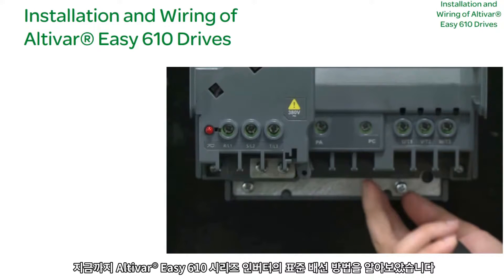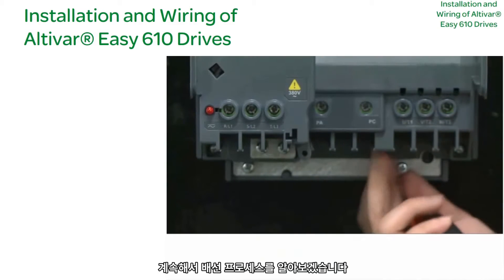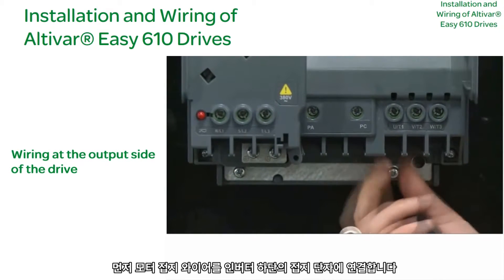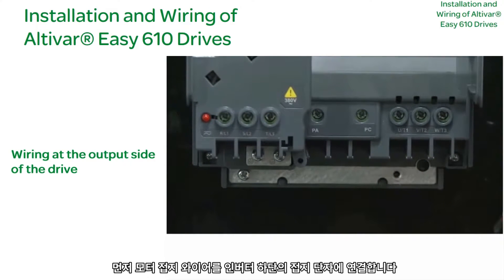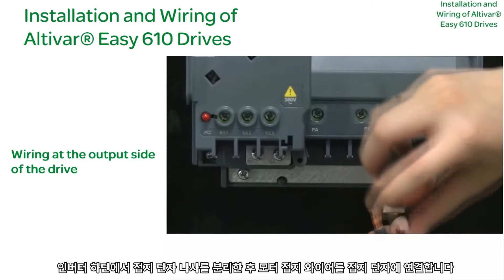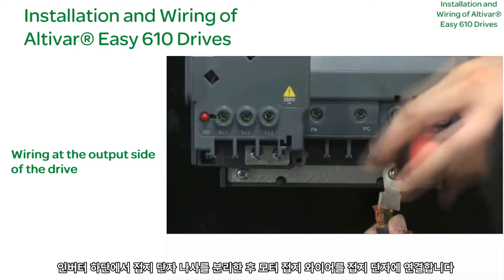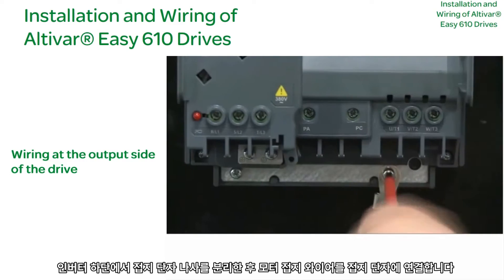Having learned the standard wiring method for our Altivar Easy 610 series drives, let's continue with the wiring process. Drive Output Side Wiring: First, connect the motor grounding wire to the grounding terminal at the bottom of the drive. Take off the grounding terminal screws at the bottom of the drive, then connect the motor grounding wire to the grounding terminal.